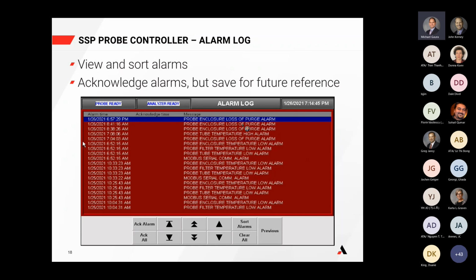These alarms that pop up here can be acknowledged by clicking down here. That can be done individually, where the end user would go through and acknowledge each alarm. They may do that because they want to keep a record of that alarm popping up, but they know that it's no longer impacting their measurement. So they may want to go ahead and acknowledge it. That effectively allows the system and the analyzer to continue operating as if there are no alarms, but the user can go back and view that alarm in the future if they want to reference it. There is the ability to acknowledge all the alarms. So maybe during a startup, when you know that you're going to have a number of alarms, you can acknowledge all of them, or you could even clear all of them. And so the user can do that here.